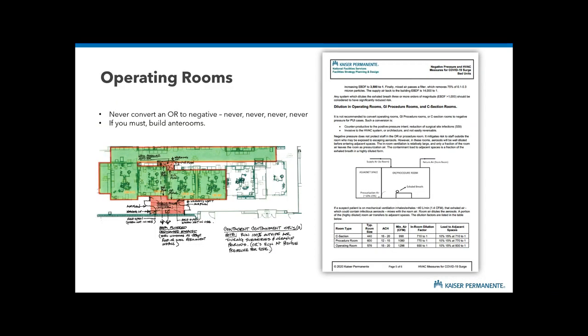So if you're in my office or an exam room with 90 CFM, then the ratio of the room air to the human breath is 450 to 1. And the ratio of the room air to the max on a breathing machine is about 65 to 1. In an OR, we have a whole lot more air. So the ratio of the room air to the exhaled breath is 6,000 to 1. The ratio of the room air to the max on a breathing machine is 1,000 to 1.